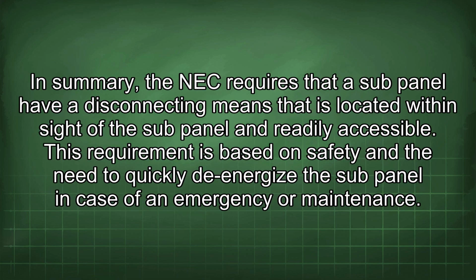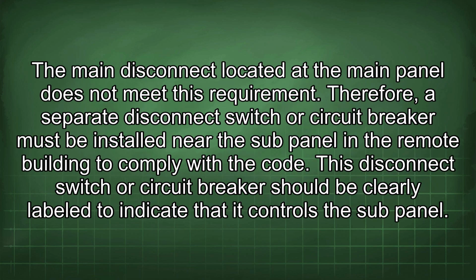In summary, the NEC requires that a sub-panel have a disconnecting means that is located within sight of the sub-panel and readily accessible. This requirement is based on safety and the need to quickly de-energize the sub-panel in case of an emergency or maintenance. The main disconnect located at the main panel does not meet this requirement.